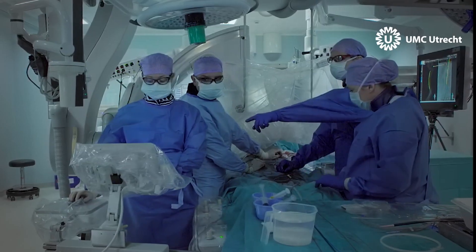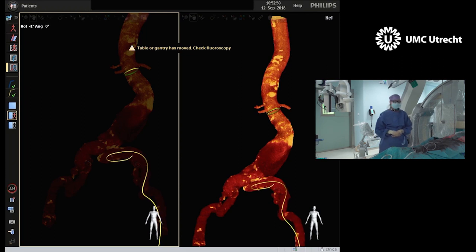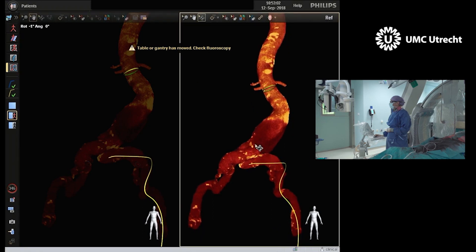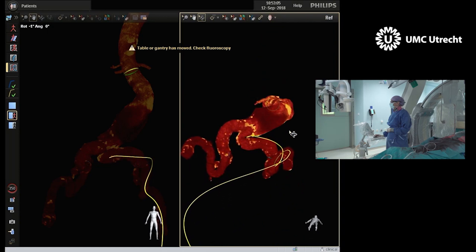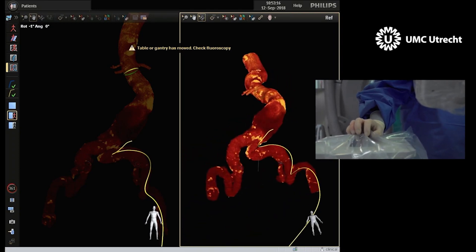There were several remarkable moments from the first-in-human study. One of the most remarkable was a case with a patient with a very tortuous iliac artery. It was hard to get through this tortuous kinked iliac artery because I couldn't see in AP how to pass this tortuosity. Then I realized that with FORCE we can use every viewing angle we want — every side viewing angle is possible, which is different from X-ray. We rotated the anatomy to an extreme craniocaudal position and then had great visibility on the kink, and passing it with the 3D device was actually quite easy.